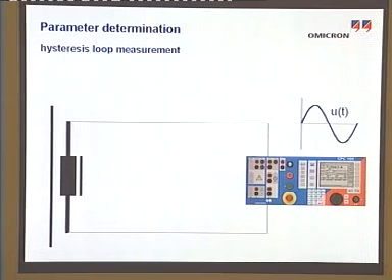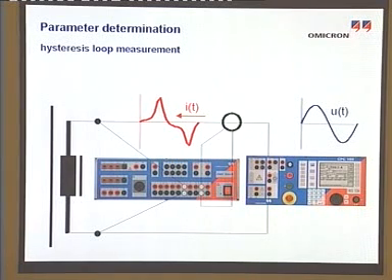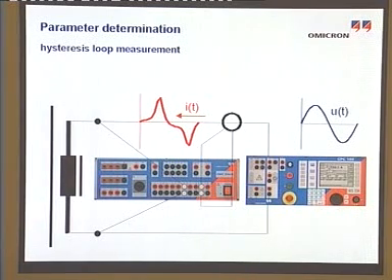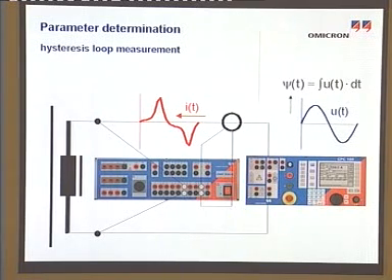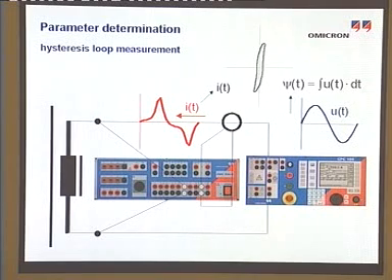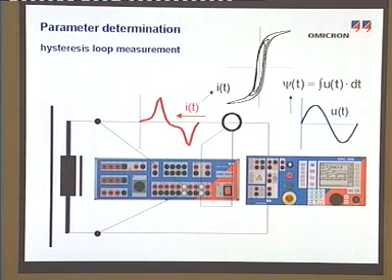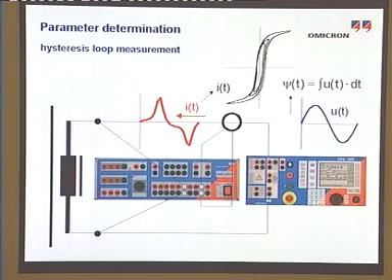The CPC100 is ideal for this. The non-sinusoidal current and the voltage are measured by the CMC256 via its analog inputs. When overlapping the magnetic flux derived from the voltage via integration and the measured magnetizing current point by point, the hysteresis loop for a specific voltage is obtained. By increasing the voltage until distinct saturation, the saturation hysteresis loop can be measured. For this, voltages up to 2000 volts are required.